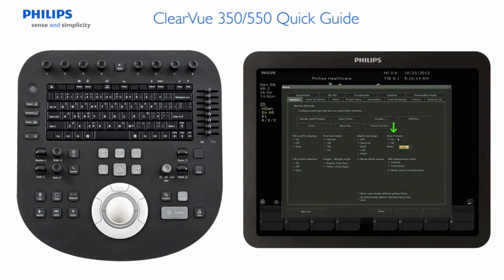Auto-freeze is enabled following a period of non-use. If this feature is turned on to a set unit of time, then the system will freeze after a period of inactivity. To release the system from the auto-freeze state, simply touch any control on the system. Note, if the system is used for invasive procedures, it is recommended that this feature be set to off. Active body marker during freeze and dual: a body marker appears on the image after freeze is pressed. The body marker will appear while in dual mode.